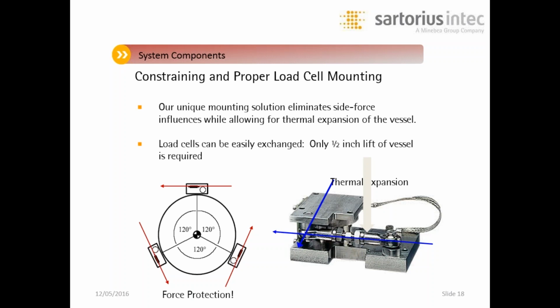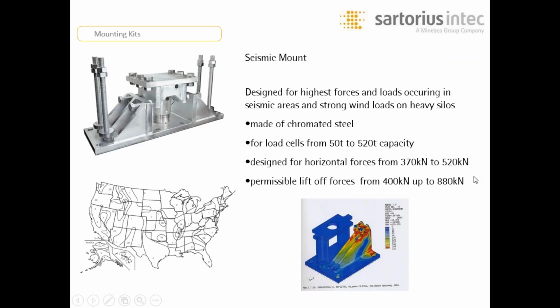Typical constraining mounts are easy to install and can be less than 2 inches tall. Removing the cells is equally simple and requires only turning the built-in jacking bolt with simple hand tools. The load cell mount can be the weakest link in a tank or silo system. Ensure the mount has been tested and is capable of withstanding all environmental forces the system could experience during operation. Specialty mounts, like the ones you see before you here, are available for specific applications.